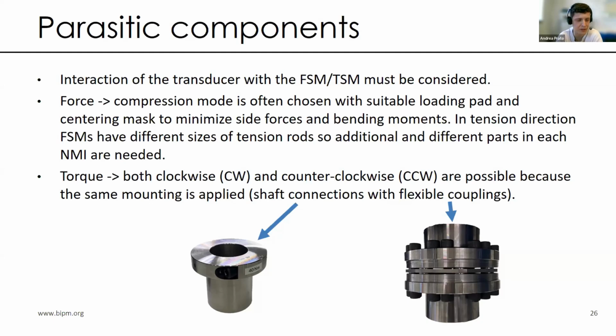Tension mode comparisons are usually neglected since the influence of adapters and different mechanical parts is not negligible. In particular, different force standard machines have different sizes of, for example, tension rods, and so more parts in each NMI are needed in order to minimize this effect. So usually this mode is not performed.